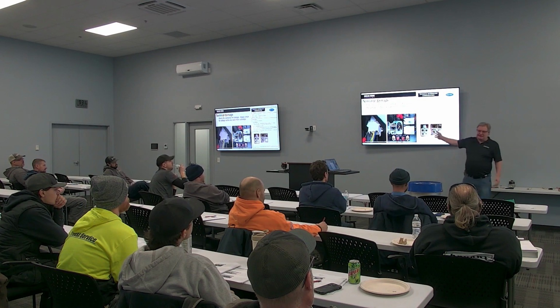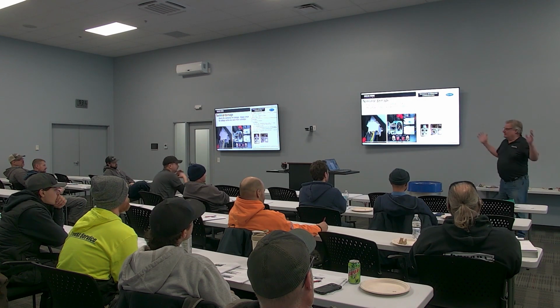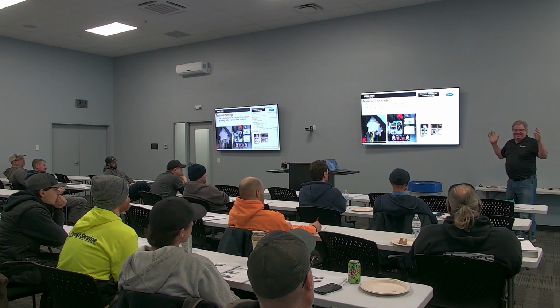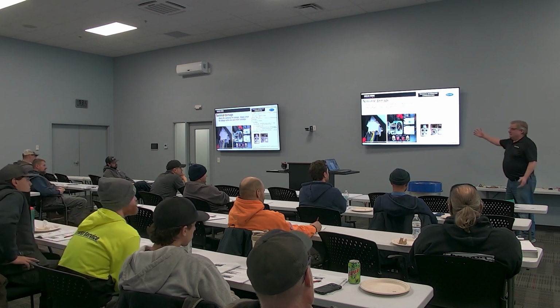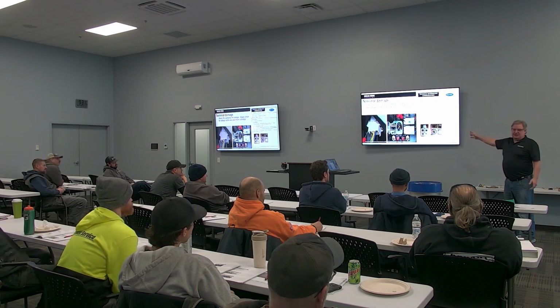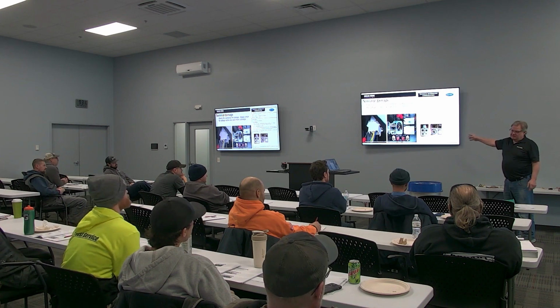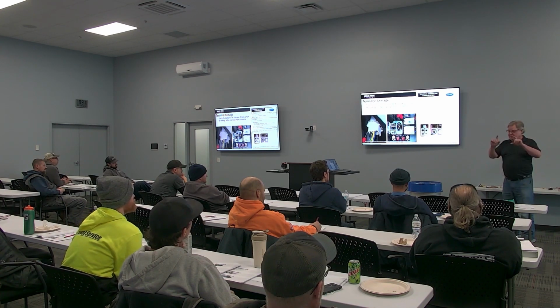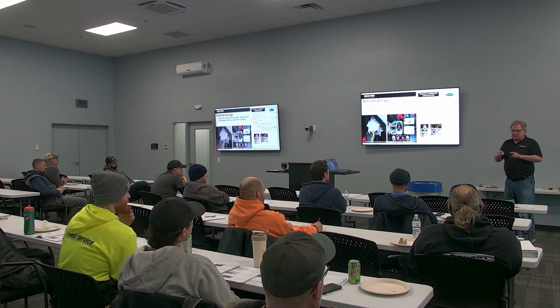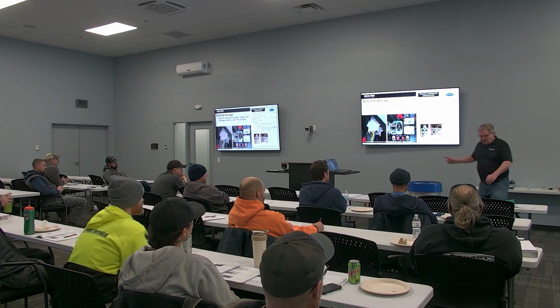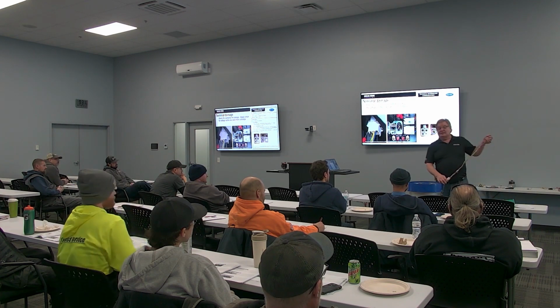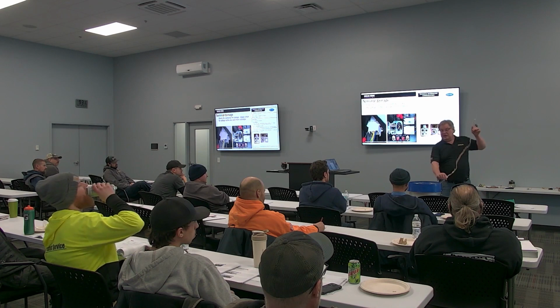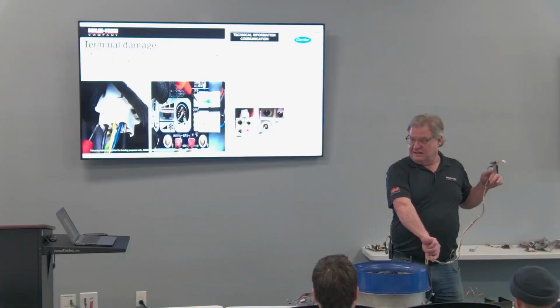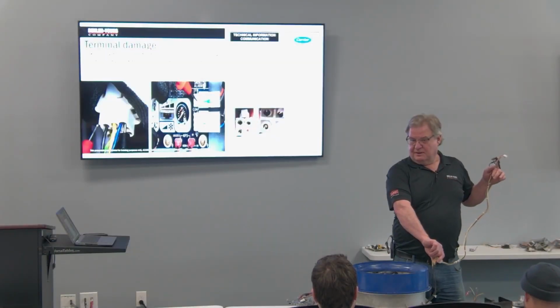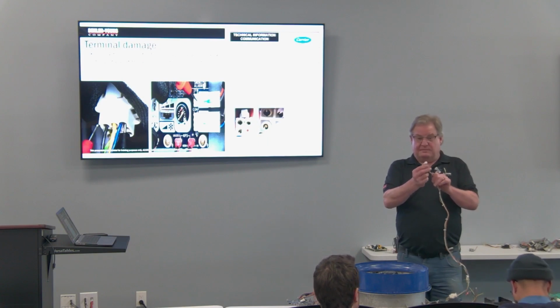so I should have caught that. All right, like I said, on the job training, right? Doing this for over 40 years, we still make mistakes. We still learn something. Okay, so do not stick your meter leads in the front of the plug. Okay, wire side, like Dave said, get you those little needle leads and get them in the wire side. And that's also why, because had I known then that I should, if I would have checked power here, I would have seen I was not getting any voltage on the gray. Okay, because this plug was not making contact.